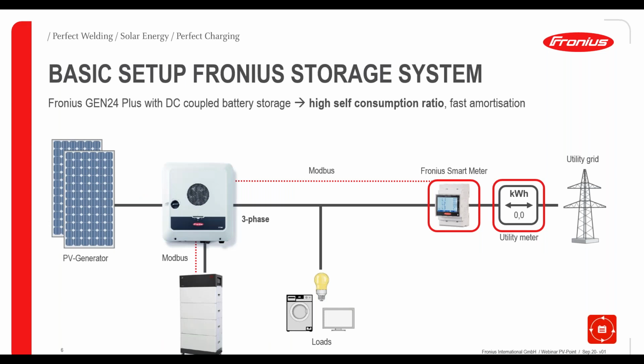Now let's have a look at the basic setup of a Fronius storage system. You start with the PV generator and the inverter, and you see the Fronius Smart Meter at the feeding point right after the utility meter. A communication line between inverter and Fronius Smart Meter is necessary: a 3-pole shielded cable, Cat5 standard. The same communication also goes to the battery. You see the BYD battery, where you connect the plus and minus poles to the Fronius Gen24 Plus inverter. The loads are in the middle. So at the feeding point we detect the surplus energy which is available, and all surplus energy not needed by the loads at the moment will be stored in the battery storage. This is the basic idea of this system.